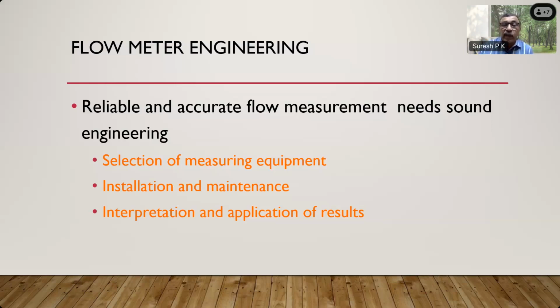So, selection of the measuring equipment. When I say selection for the required accuracy, as we discussed earlier, for 2% accuracy you don't go for a mass flow meter. For 3% accuracy, you don't go for a mass flow meter. For 0.5% accuracy, maybe a turbine flow meter is sufficient. For 0.2% accuracy, you may select a mass flow meter or maybe a modern ultrasonic flow meter. That again depends on what the law mandates. As Agarwal sir earlier rightly pointed out, as per OIML, certain classes of meters need certain accuracies. So if a particular measurement needs that accuracy, then you cannot go for an instrument inferior to that, because the law mandates such accuracies. So selection of measuring equipment for your requirement is very important.